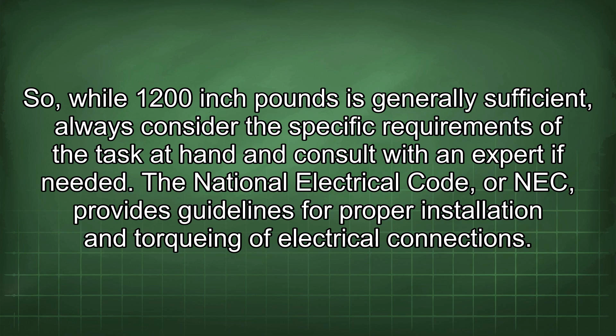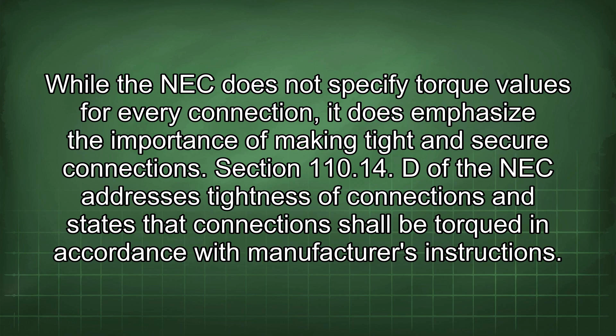The National Electrical Code, or NEC, provides guidelines for proper installation and torquing of electrical connections. While the NEC does not specify torque values for every connection, it does emphasize the importance of making tight and secure connections. Section 110.14(D) of the NEC addresses tightness of connections and states that connections shall be torqued in accordance with manufacturer's instructions. If manufacturer's instructions are not available, recognized industry practices should be followed.